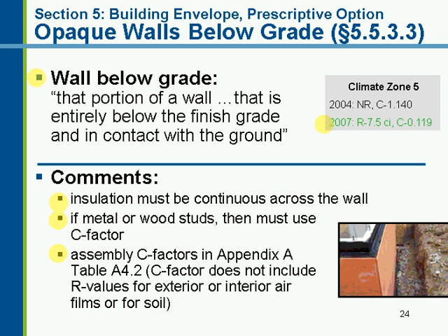The challenge with soil is that the conductivity varies widely around the country, and it also varies depending on the moisture content of the soil. And these things are such a wild card and hard to get good information on that ASHRAE decided to make the standard simpler and just specify the assembly that you're constructing itself and not include the R values. I will tell you, though, that the decisions on what the criteria should be were based on analysis that included the effect of the soil. And when you go to the ENVSTD program, when you go through that process, it does include some buffering effect for the soil. But that was also used in setting the prescriptive criteria, so it doesn't mean that it's going to lead to any different results.